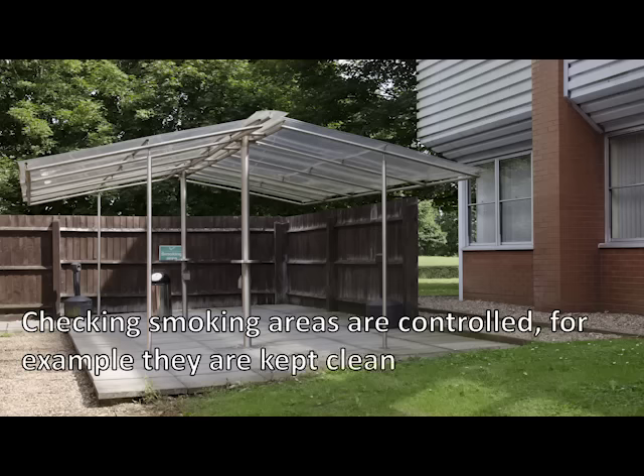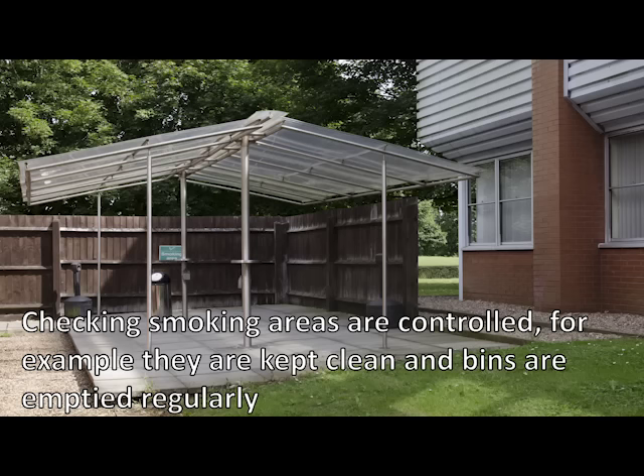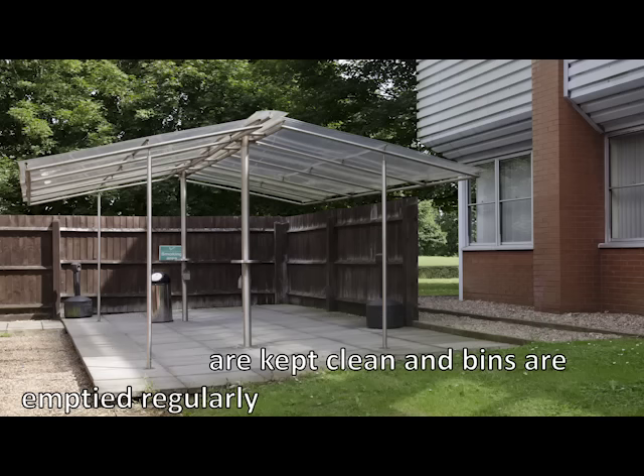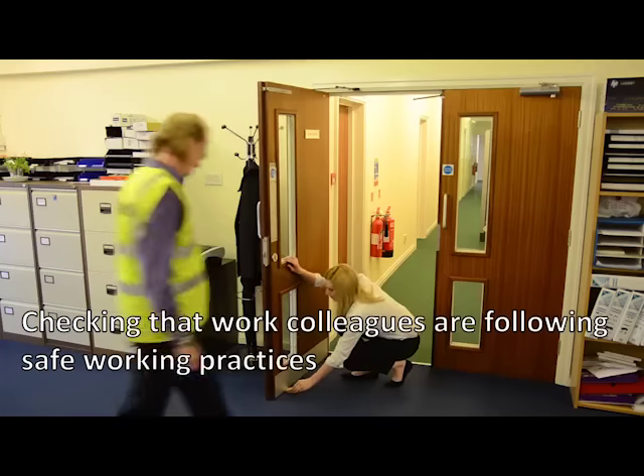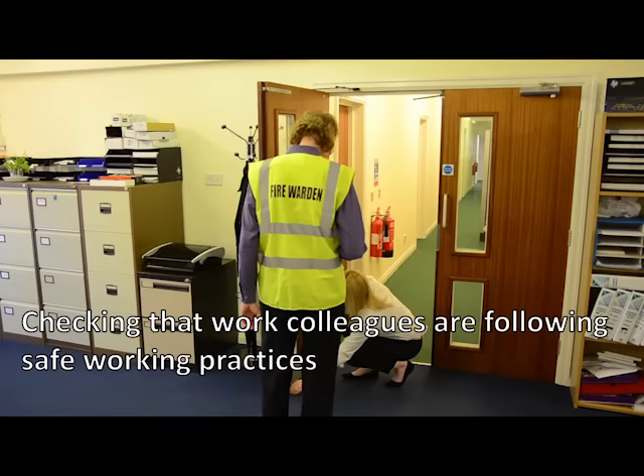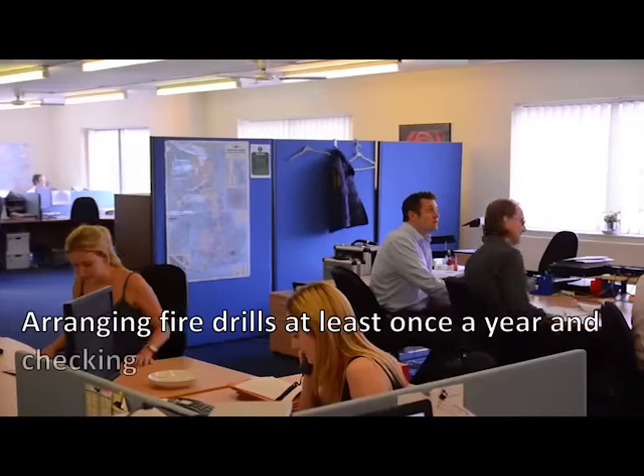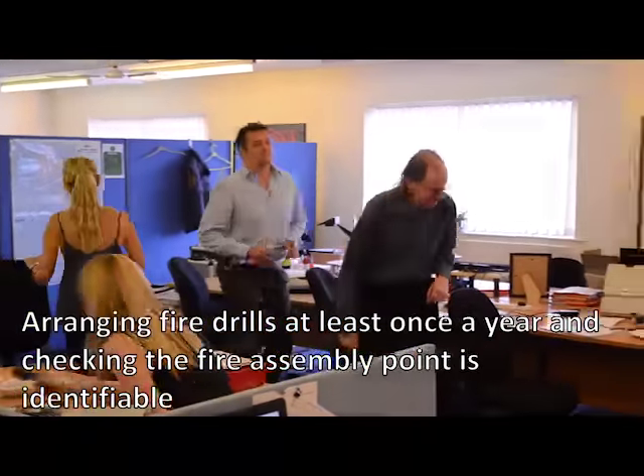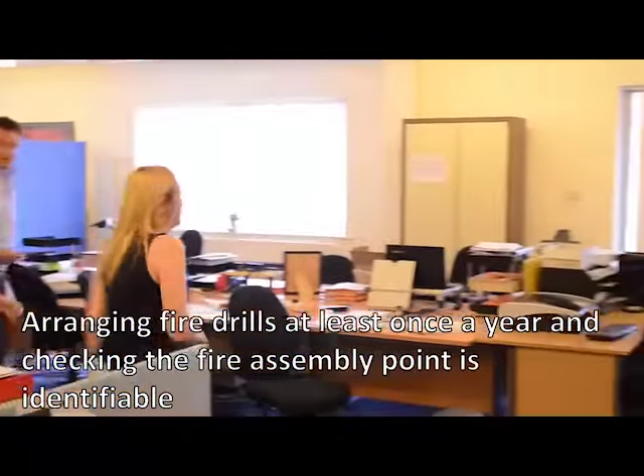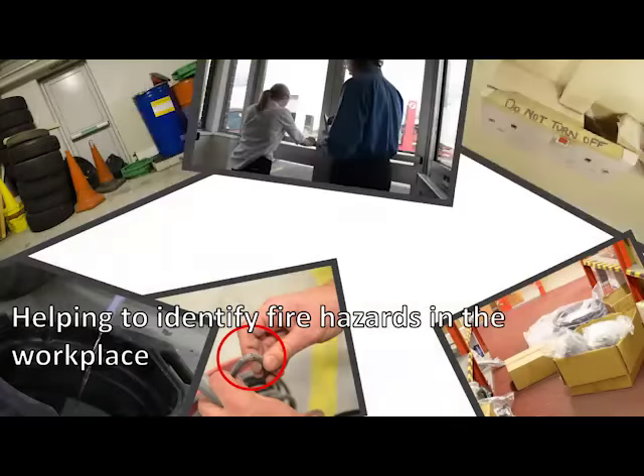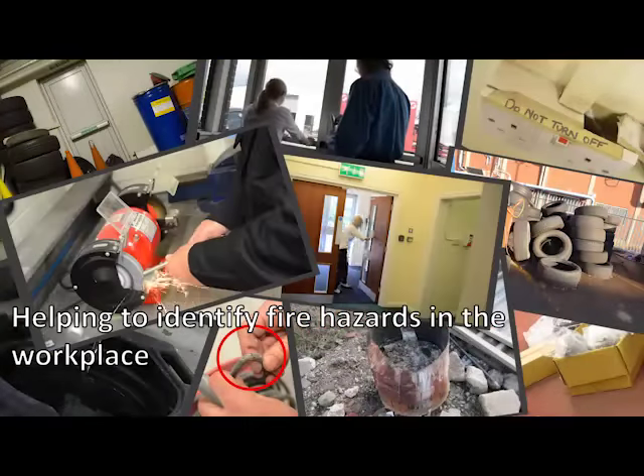Checking smoking areas are controlled. For example, they are kept clean and bins or other receptacles for smokers' materials are emptied on a regular basis. Checking that work colleagues are following safe working practices, arranging fire drills at least once a year and checking the fire assembly point is clear and easily identifiable, and finally, helping to identify fire hazards in the workplace.